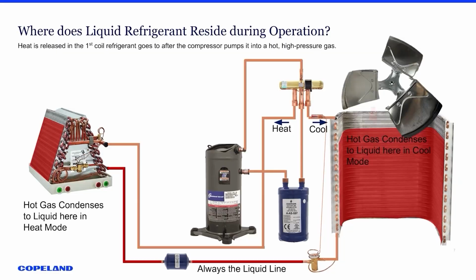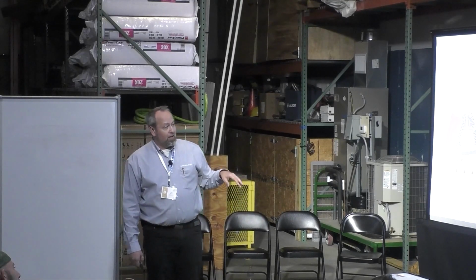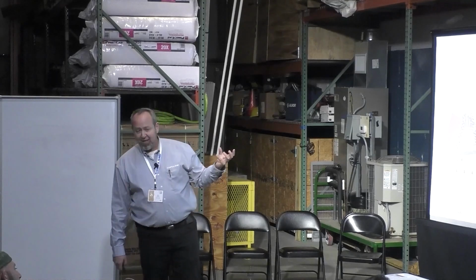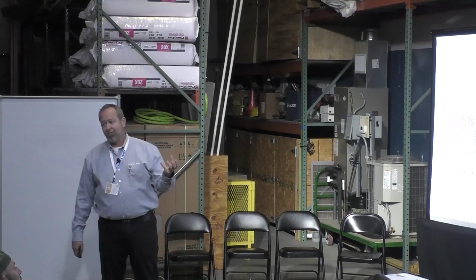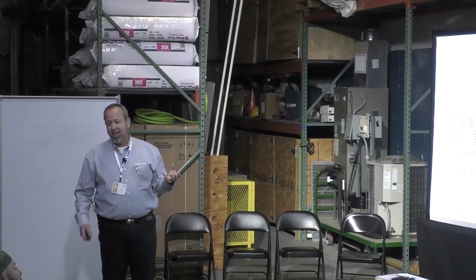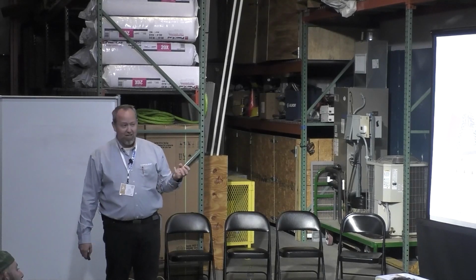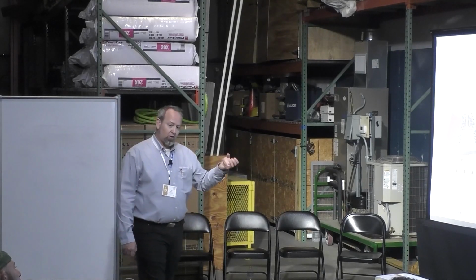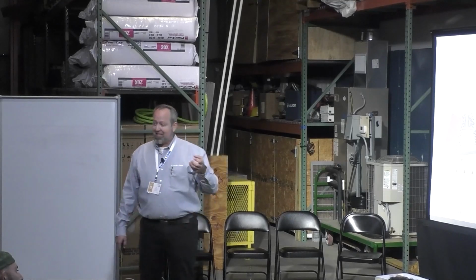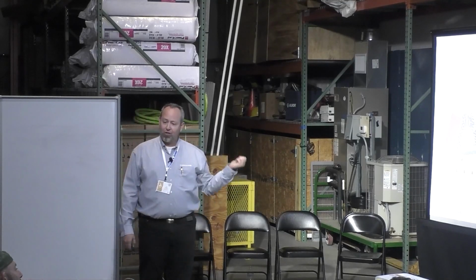The second slide here is basically the opposite of what we just showed you, where the coil inside gets hot and releases the heat, and the coil outside absorbs the heat. And that heat that it's absorbing is sometimes not very much. So it's taking a lot of that coil space to be able to absorb that heat, to actually boil that refrigerant off to get it in a vapor form back to the compressor.